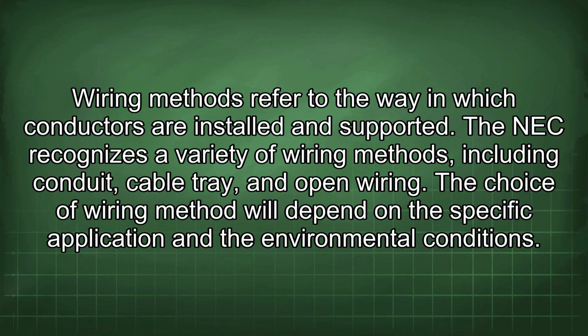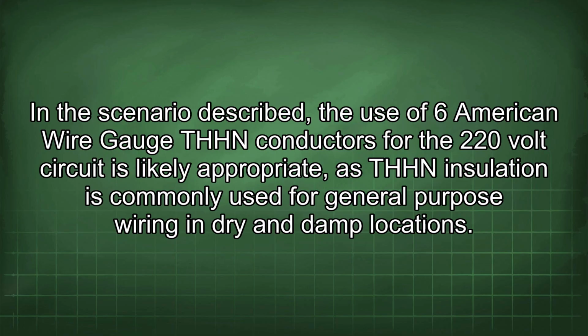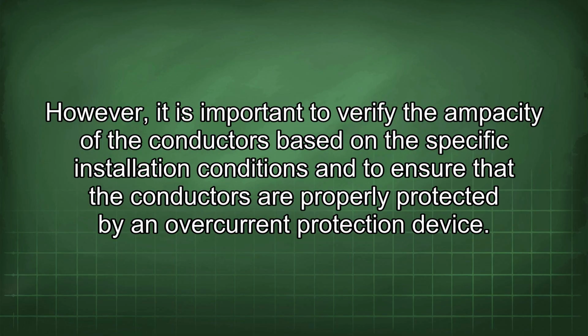Wiring methods refer to the way in which conductors are installed and supported. The NEC recognizes a variety of wiring methods, including conduit, cable tray, and open wiring. The choice of wiring method will depend on the specific application and the environmental conditions. In the scenario described, the use of 6 American wire gauge THHN conductors for the 220-volt circuit is likely appropriate, as THHN insulation is commonly used for general-purpose wiring in dry and damp locations. However, it is important to verify the ampacity of the conductors based on the specific installation conditions and to ensure that the conductors are properly protected by an overcurrent protection device.